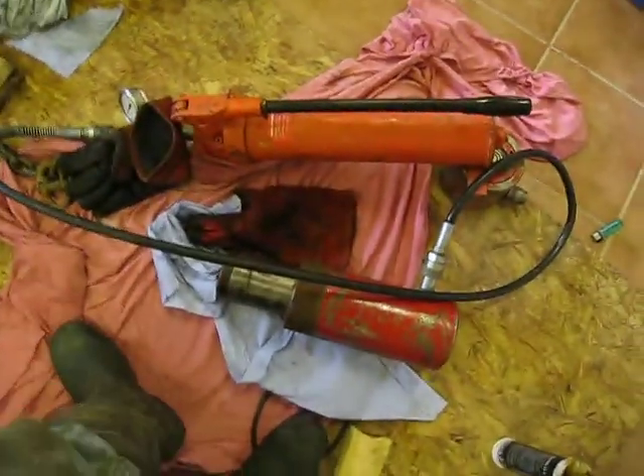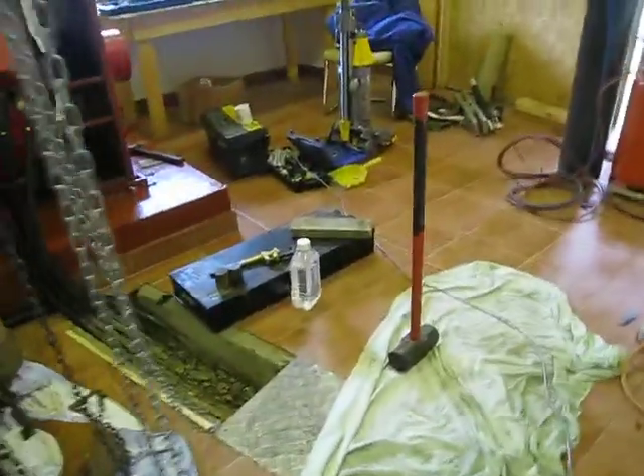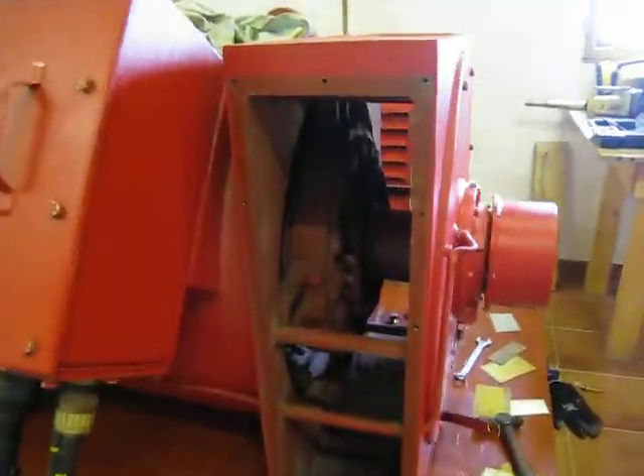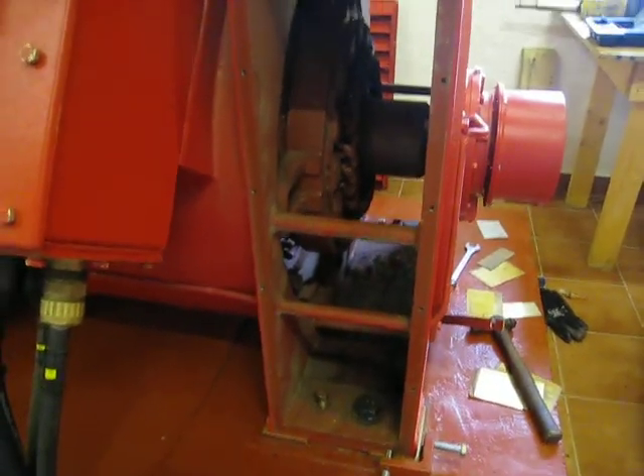We're pressurized and ready for some water. There's the hydraulic puller we use to pull that coupling off — nice clean windings. Removing a few midges and dead flies from inside there.